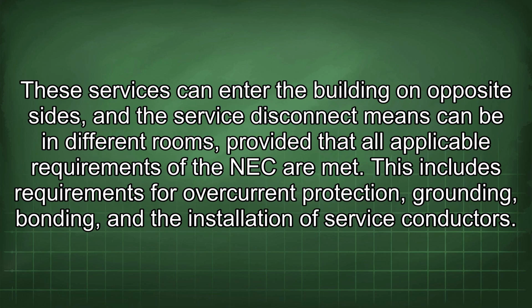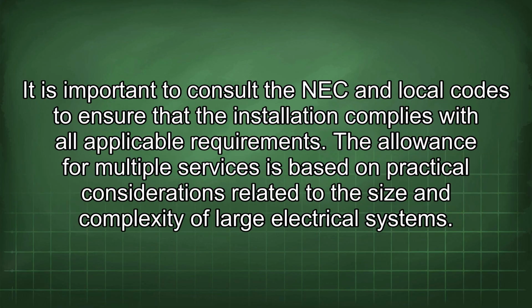These services can enter the building on opposite sides, and the service disconnect means can be in different rooms provided that all applicable requirements of the NEC are met. This includes requirements for overcurrent protection, grounding, bonding, and the installation of service conductors. It is important to consult the NEC and local codes to ensure that the installation complies with all applicable requirements.